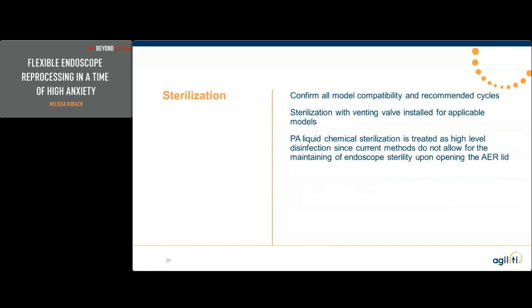Sterilization: we want to confirm all model compatibility and recommended cycles. Sterilization with venting valves installed, of course, for applicable models. And also some of the liquid chemical sterilization has to be treated as if it were high-level disinfected when it comes to storage, since current methods do not allow for maintaining of endoscope sterility upon opening the AER lid for the tabletop models that are unable to contain the item.